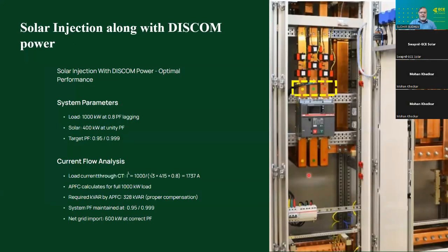So to summarize, what ideally we are doing is this is your power input from DISCOM, this is your breaker, and these are your CTs, maybe for metering, maybe for APFC or whatever. This is the point where I was trying to tell you that we must inject solar power at this particular point. Now this is very well taken care by most of you, and this is no more a problem because, as we discussed, for large consumers a slight imbalance in the load really doesn't matter much, and that kind of deviation in reactive power compensation requirement can be handled by APFC.